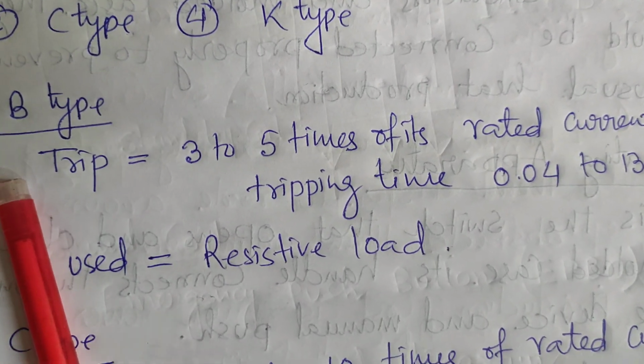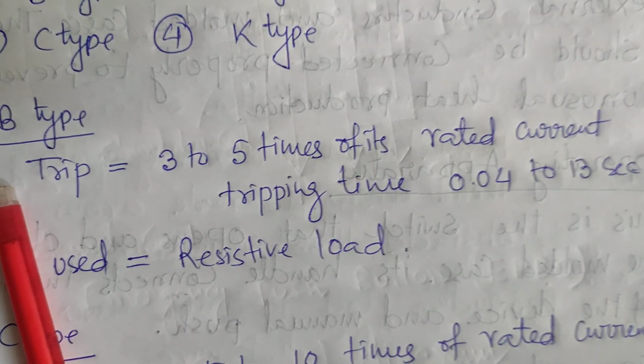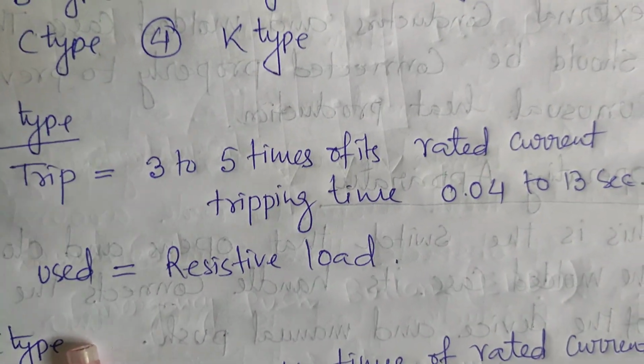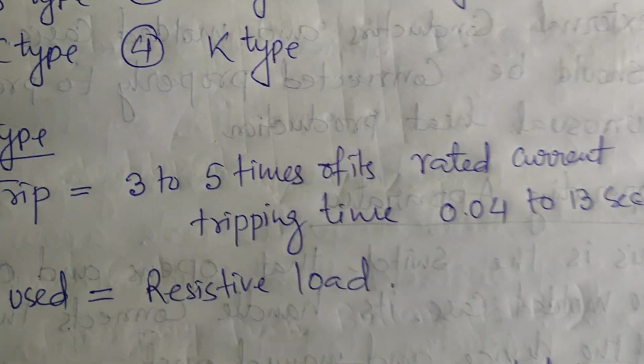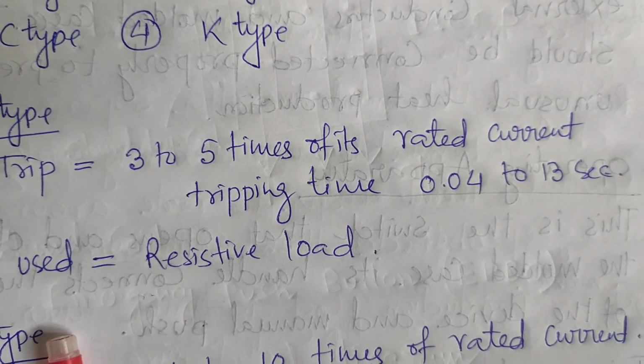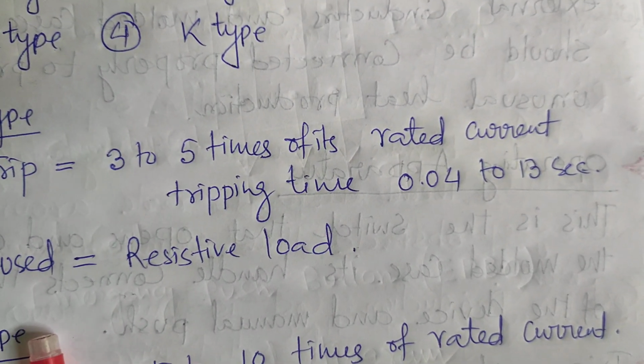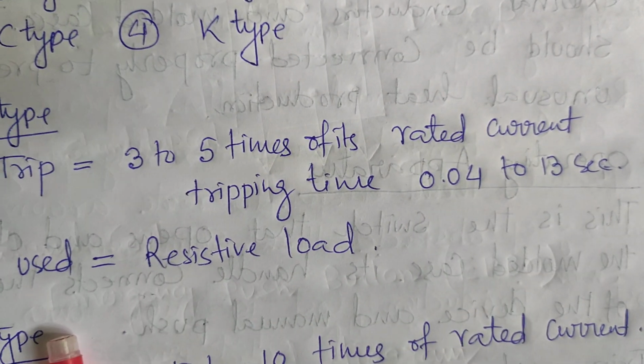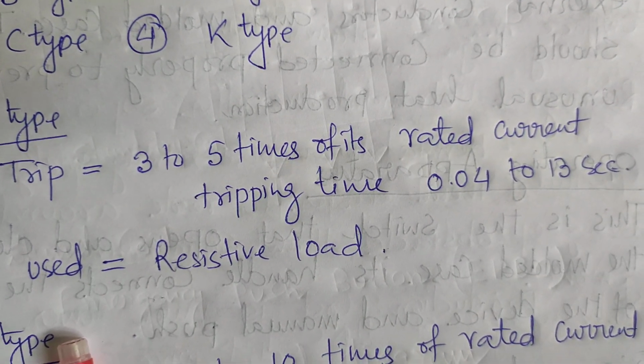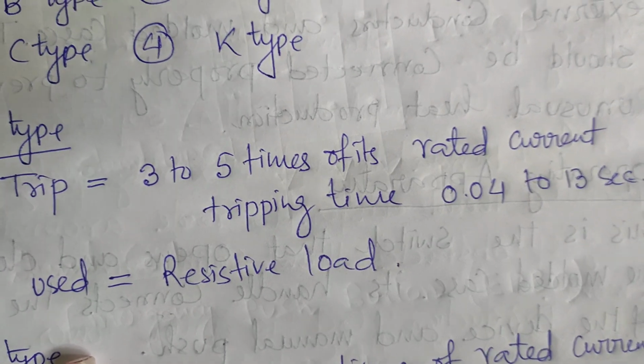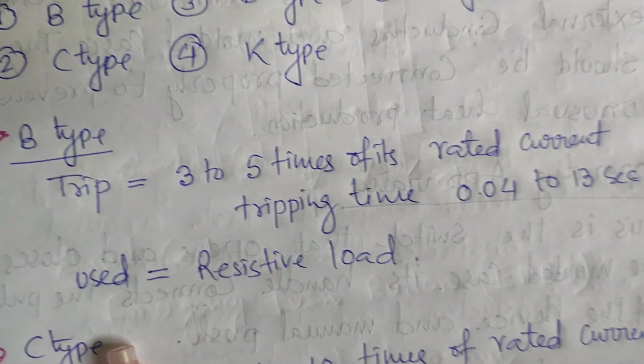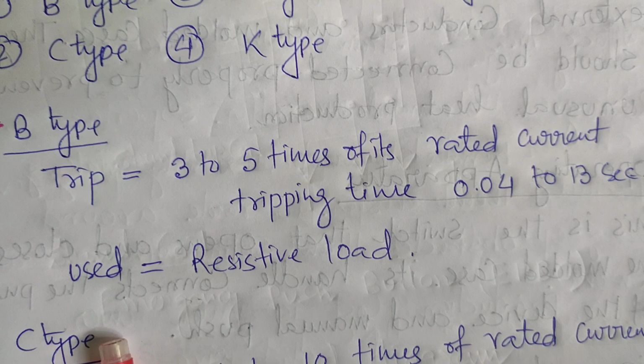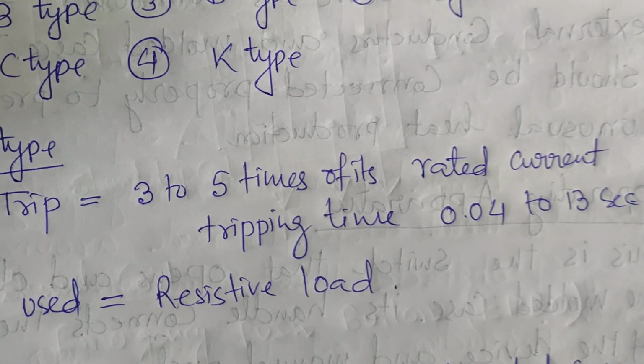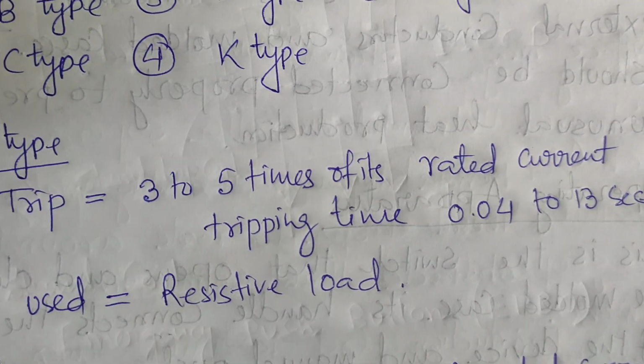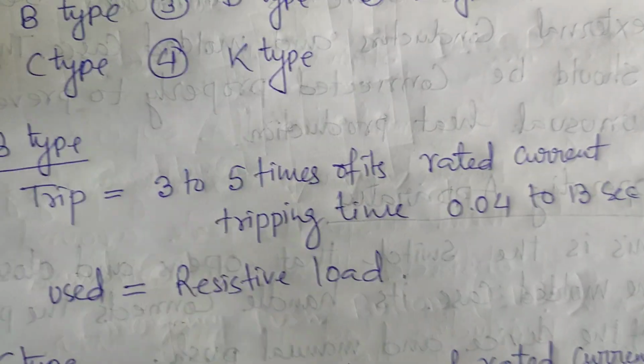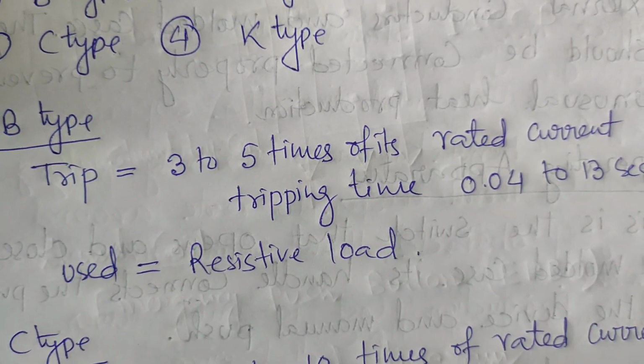It depends on the tripping features. If 3 to 5 times the rated current flows, the tripping time will be 0.04 to 13 seconds. Within this time period, at this many times the rated current, this type of MCCB will trip. This type of MCCB is actually used for resistive loads. If there is a resistive load, you have to choose the B type MCCB.